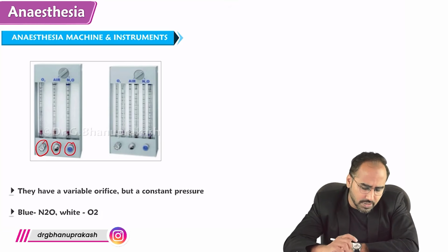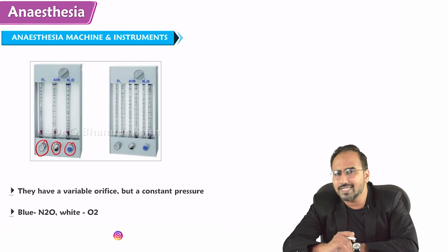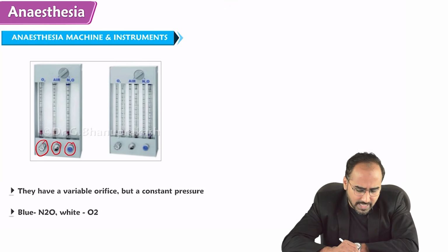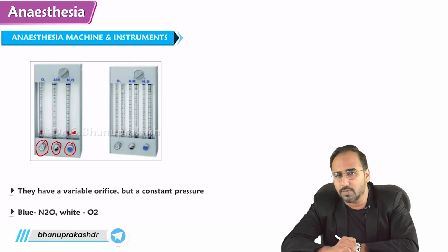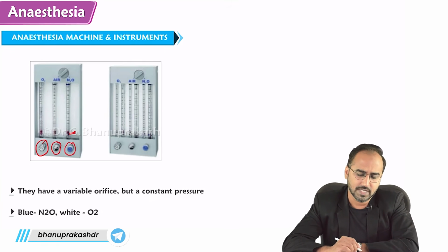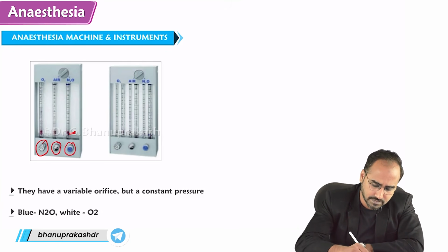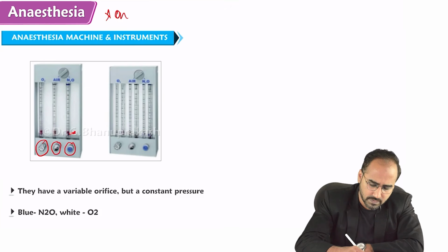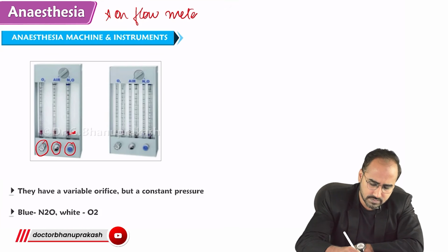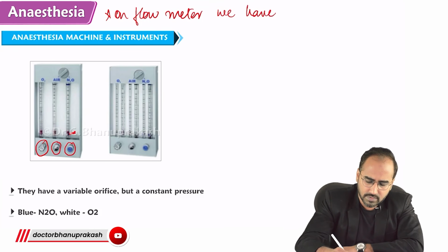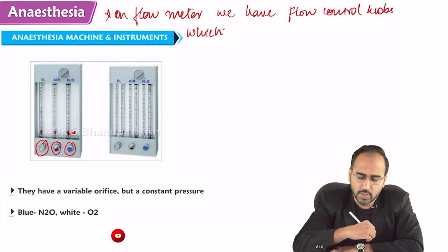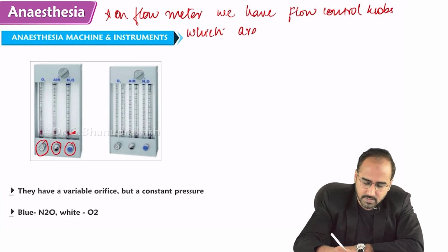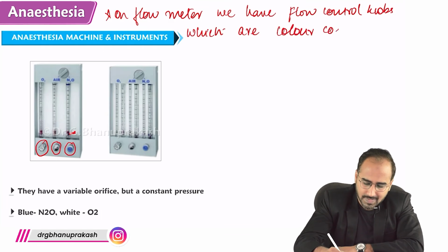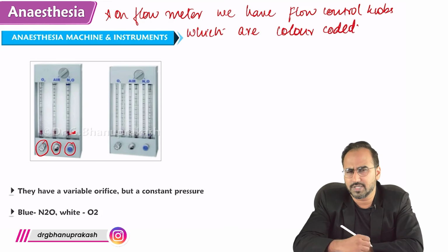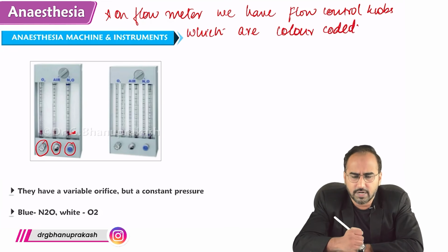As you rotate the flow control knob in anti-clockwise direction, what rises up? There is a small structure inside the flow meter called the bobbin. This bobbin rises up. So remember guys, on the flow meter, you can write from here: on the flow meter, we have flow control knobs which are color coded, so that you can identify. Apart from being color coded, they are also labeled.